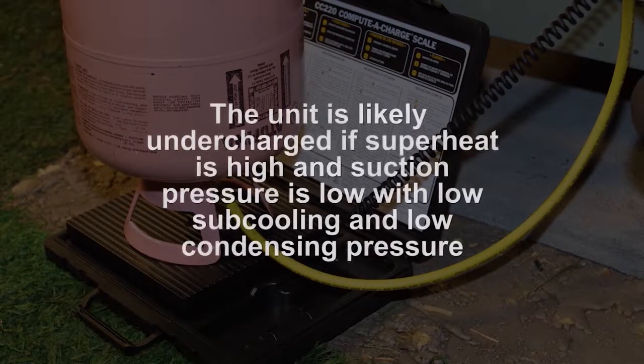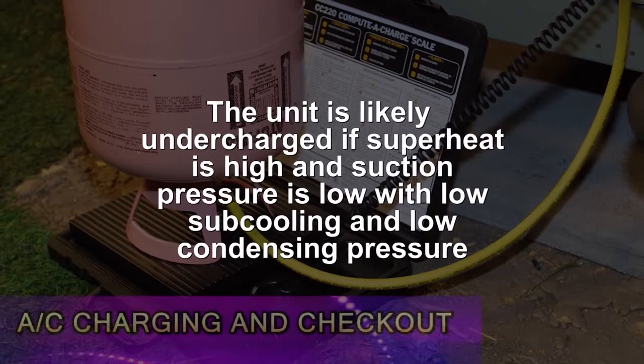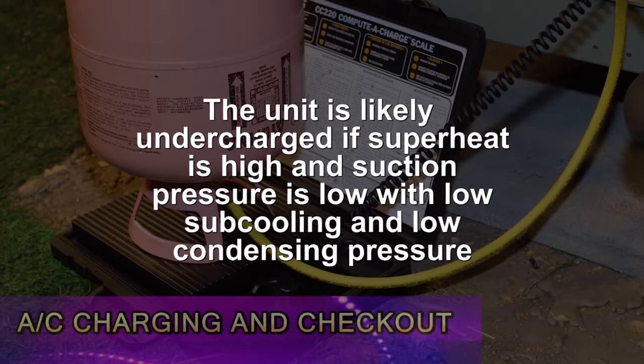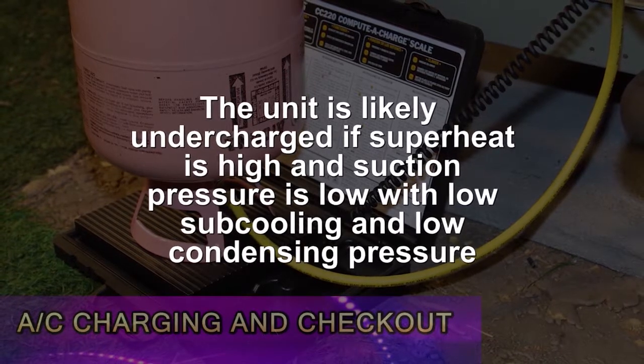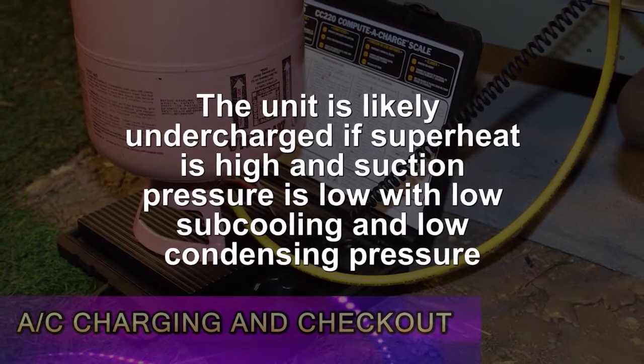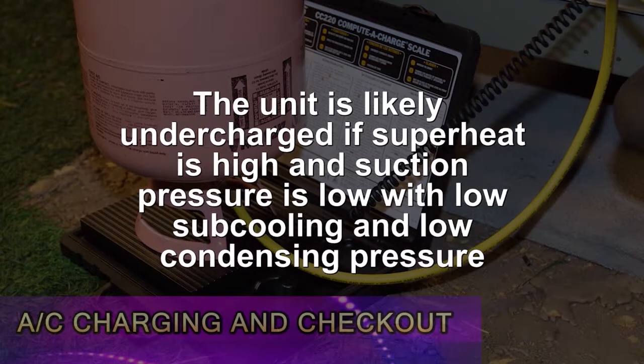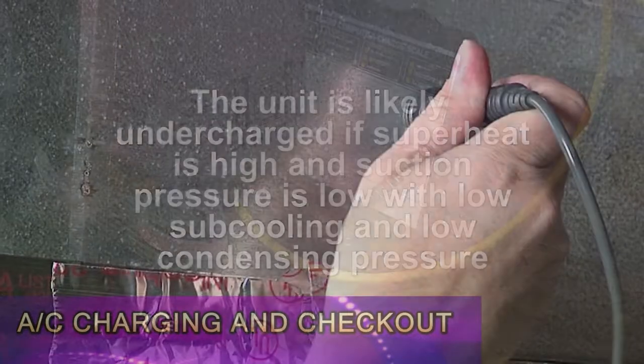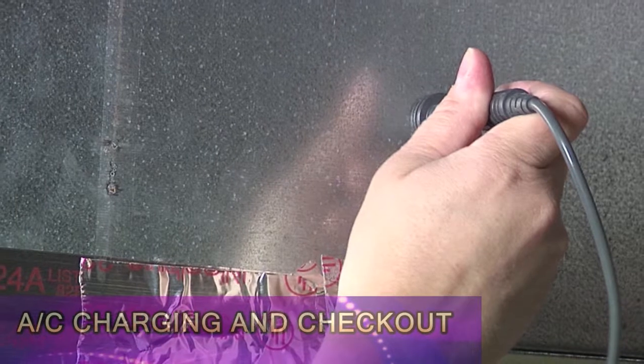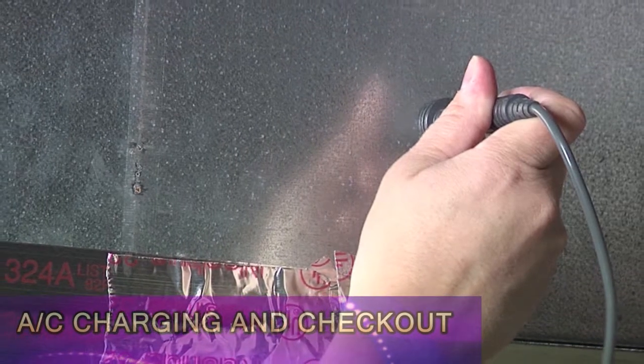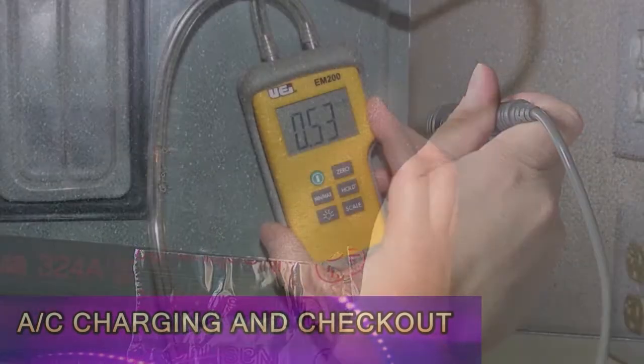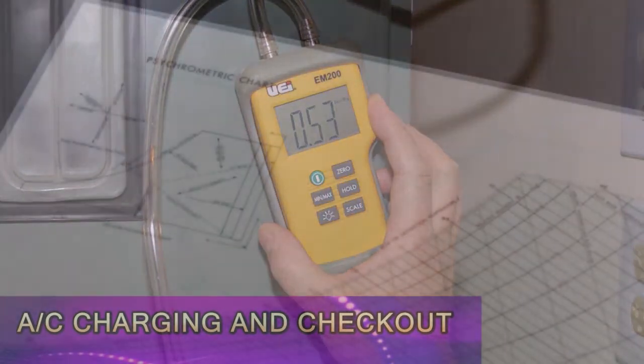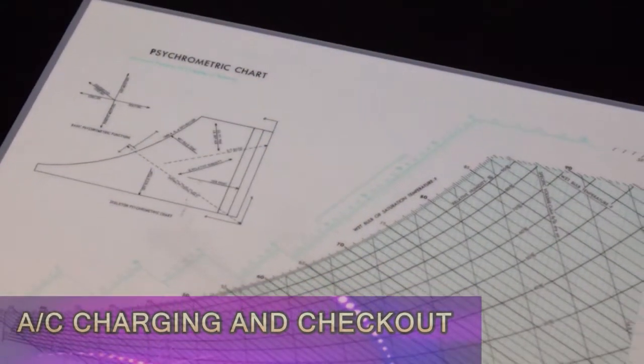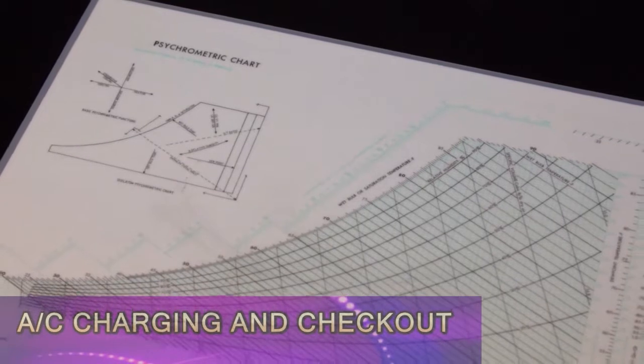A fundamental rule for charging will get the technician close to the condition of charge. If superheat is high and suction pressure is low with low subcooling and low condensing pressure, the unit is likely undercharged. An additional option is to run a cooling capacity check using the temperature difference across the evaporator, the airflow over the coil, and a psychrometric chart to demonstrate the capacity loss that will add to operating expenses.